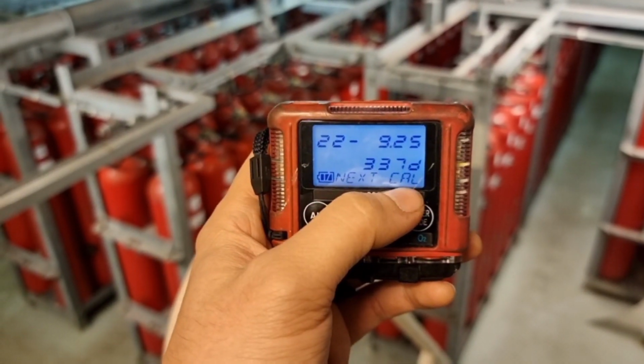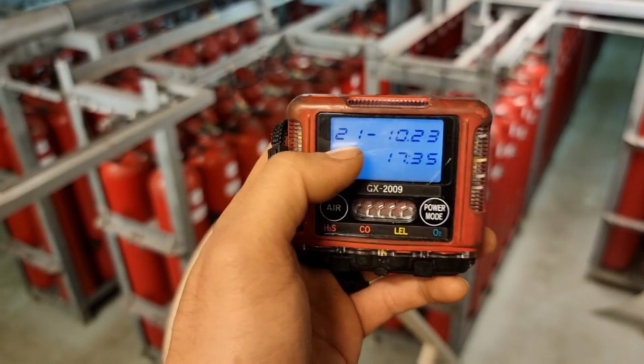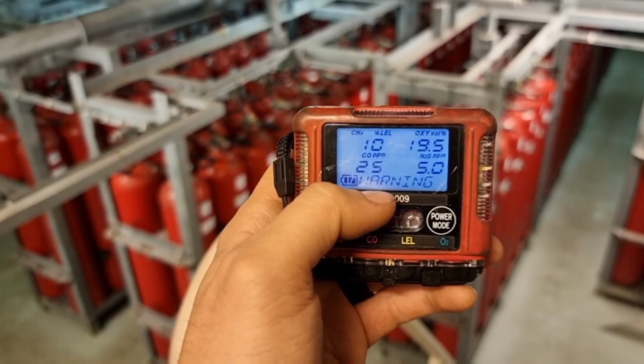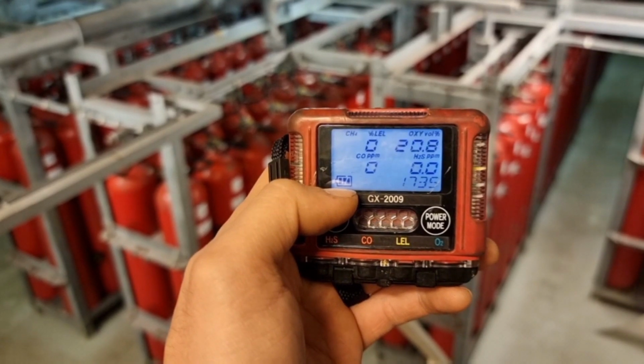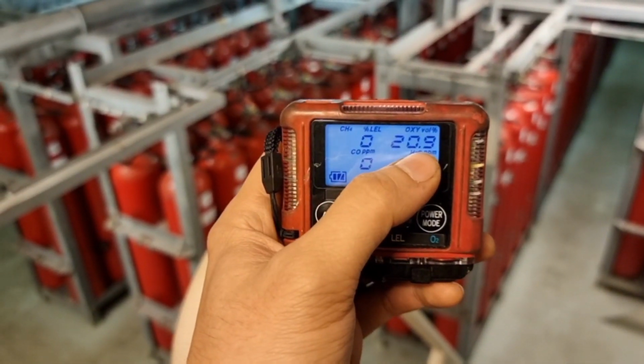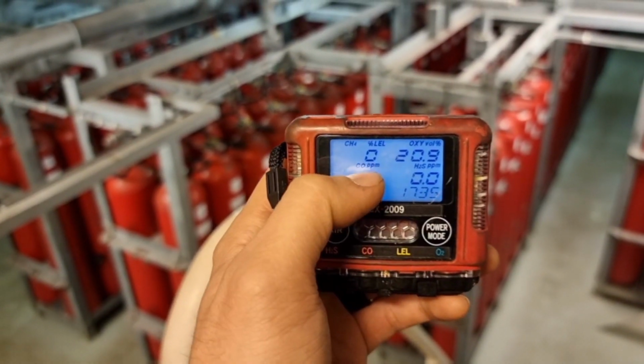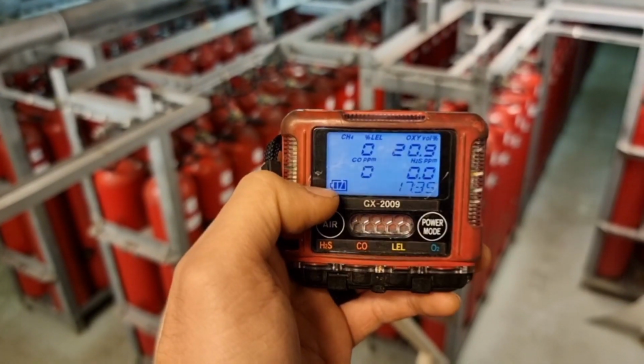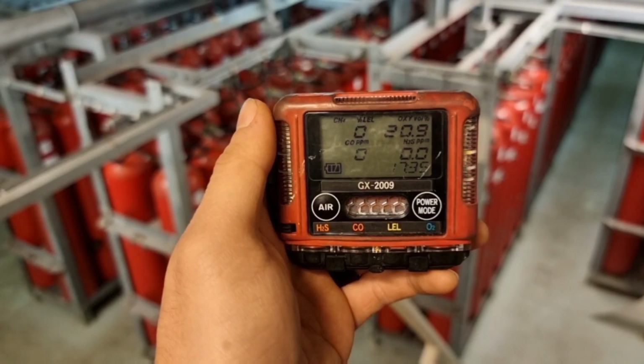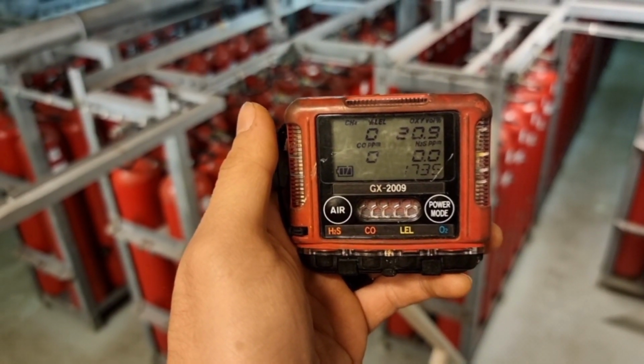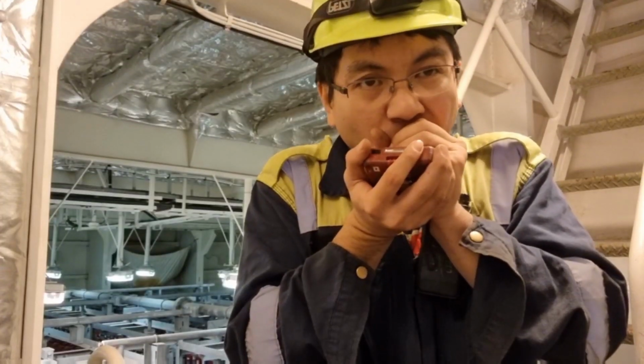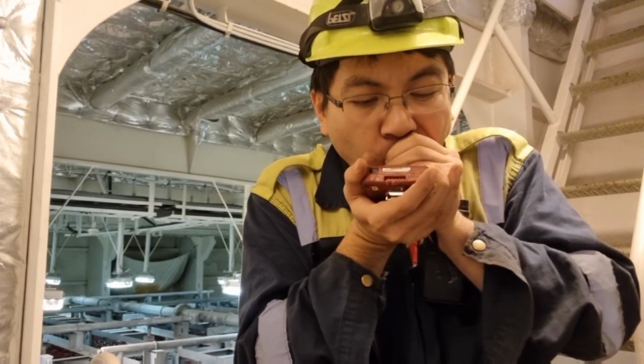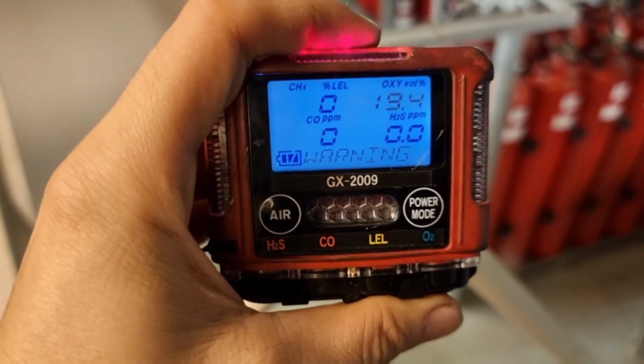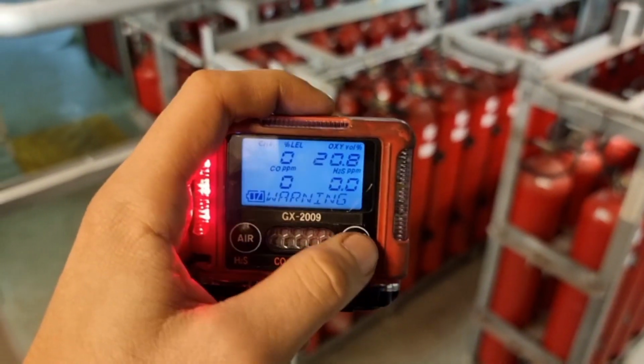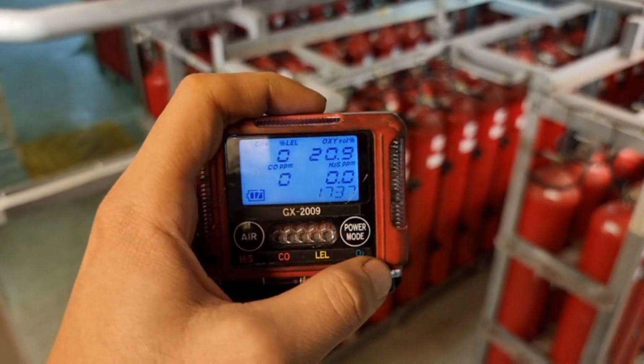Just a quick familiarization, once we switch on this device, you will see the last date it was calibrated, the next day of calibration, and the battery percentage of this device. As you can see, we are measuring 20.9 oxygen level. To ensure that this device is working fine, we need to test if the alarm will sound once the oxygen level goes down. So what I will do is to blow CO2 onto the device to reduce the oxygen level it is measuring. And this is the sound you will hear once it is activated. So once you hear this alarm, then you need to evacuate the area.